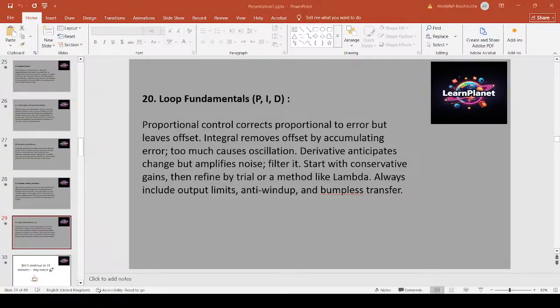Proportional corrects proportionally to error but leaves steady-state offset, as we said. Integral removes offset by accumulating errors but risks windup and oscillation if aggressive. Derivative anticipates change but amplifies noise and must be filtered. Practical tuning starts conservatively. Use relay, Ziegler-Nichols, or model-based methods like lambda, and then refine with process knowledge. Always set output limits, anti-windup, rate limits, and bumpless transfer for manual-auto transition. Example: for level control on a surge tank with slow dynamics, prioritize P and I. Keep derivative low or disable it, and include bumpless transfer for operator intervention.